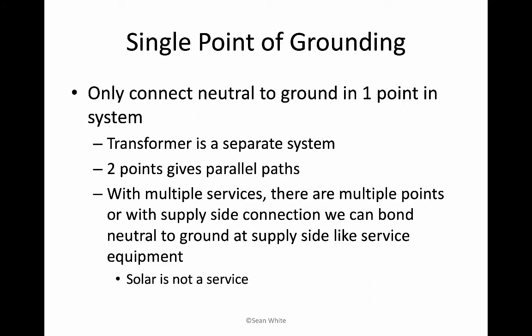And even a supply side connection, sometimes known as a line side tap, but more correctly known as a supply side connection, when you're hooking up solar, which we're going to learn a whole lot about in 705.11. That's 2020 NEC is 705.11. 2017 NEC is 705.12(A). Anyway, a supply side connection is connected like a service oftentimes. And so you could separately bond your neutral to ground when you're doing a supply side connection. Although solar is not considered a service, so even when you are doing a supply side connection, it is not a service, and you're not required to follow Article 230 services, which we already covered a bit, except for where it directs you to Article 230.